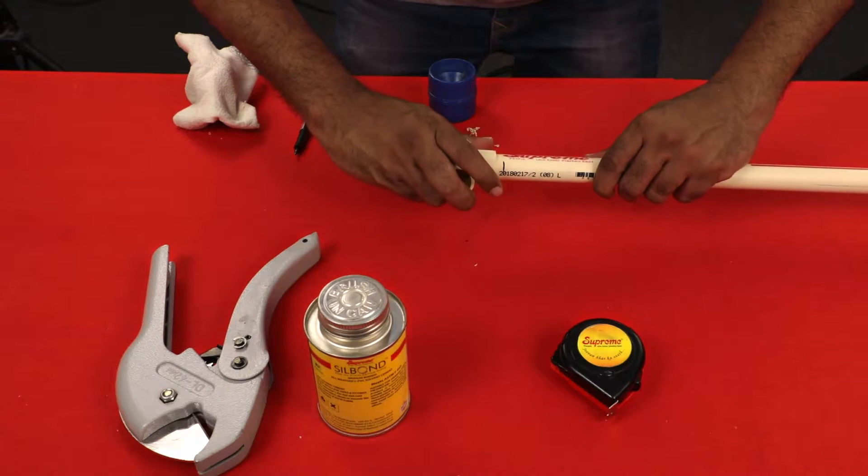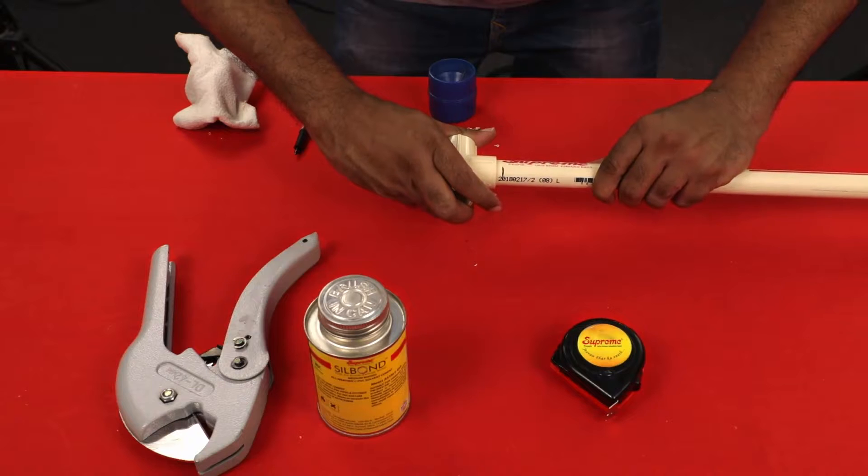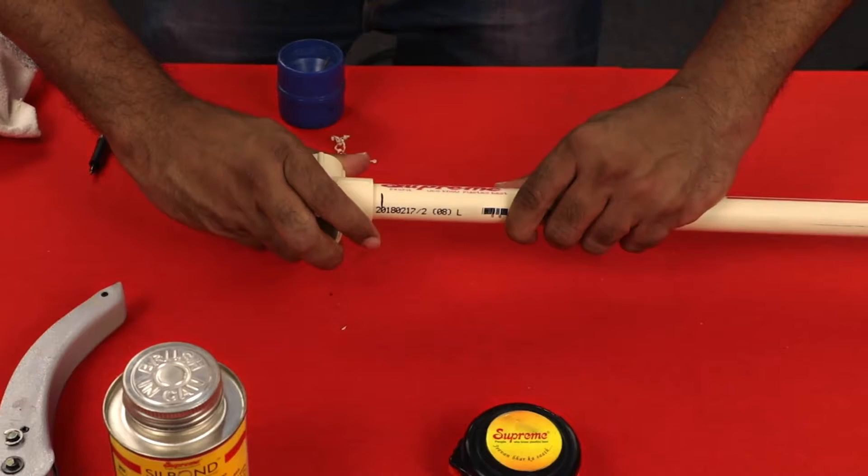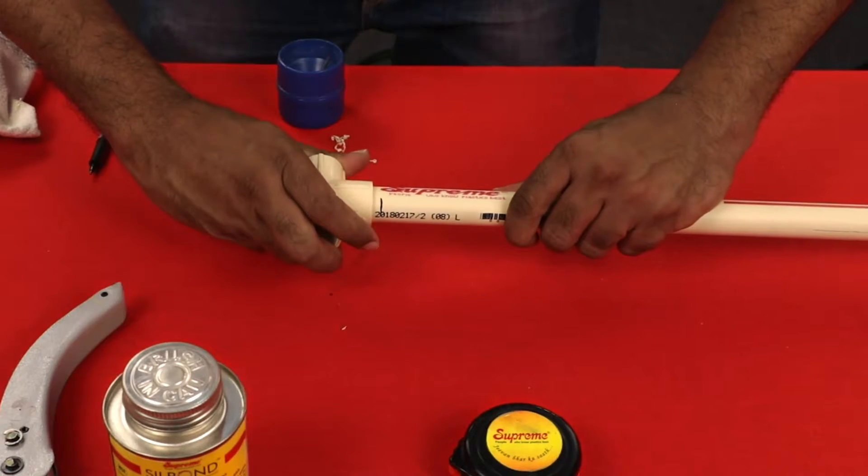Insert the pipe into the fitting and check that the interference occurs at about one-third to two-third of the socket depth. Too tight or too loose fitting may lead to leakages.